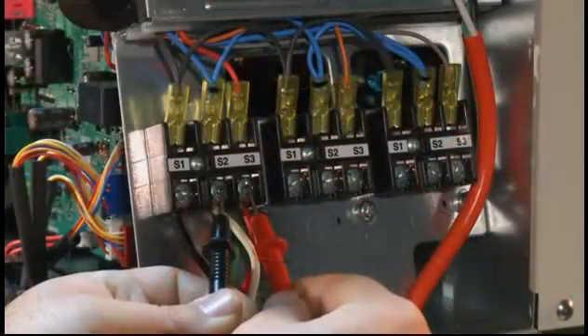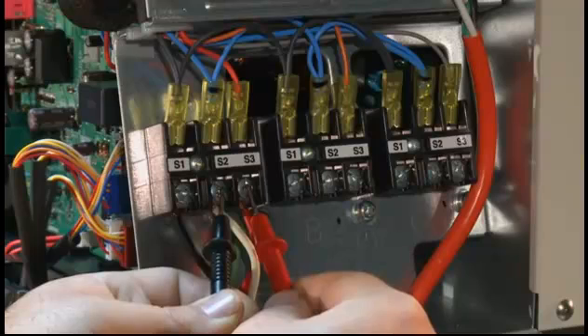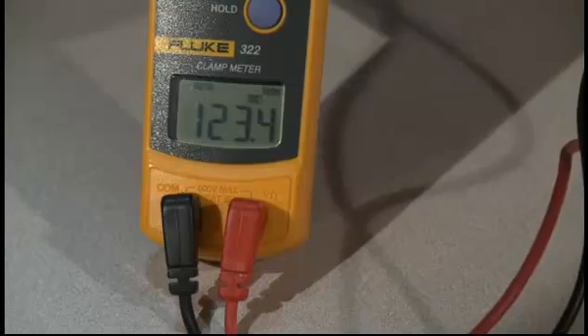The last and most common thing that could cause a communication error would be crossed wires, and this is usually noticed on startup. If you were to check your DC voltage at S2 and S3 on the outdoor unit with the wires connected and see a high voltage DC somewhere around 80 to 120 volts DC, that would indicate that S1 and S2 are swapped.